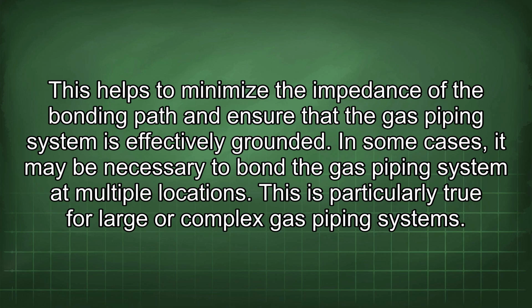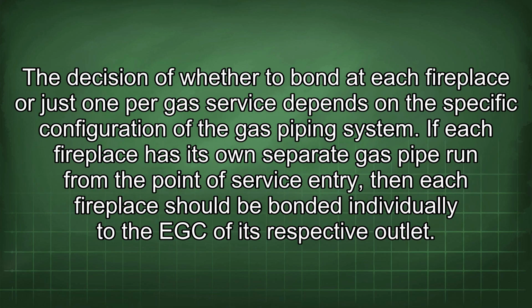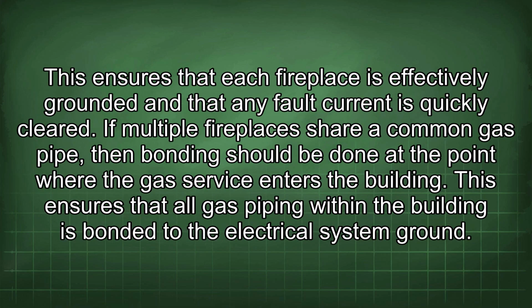In some cases, it may be necessary to bond the gas piping system at multiple locations. This is particularly true for large or complex gas piping systems. The decision of whether to bond at each fireplace or just one per gas service depends on the specific configuration of the gas piping system. If each fireplace has its own separate gas pipe run from the point of service entry, then each fireplace should be bonded individually to the EGC of its respective outlet. This ensures that each fireplace is effectively grounded and that any fault current is quickly cleared.